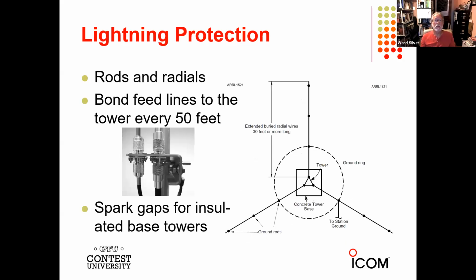Okay, lightning protection. Rods and radials. Here's your tower. How do you protect a tower? I think everybody's seen the picture in the handbook where you've got a triangular lattice tower. This is looking down onto the tower. Each leg has a heavy connector that goes to a ground rod, and then those are all connected together with a ground ring. That's a great thing. If you really want more protection, run a big heavy radial out from that ground rod another 30 feet or so and bury it. Put in some more ground rods along it.